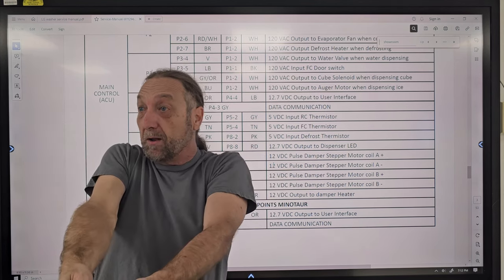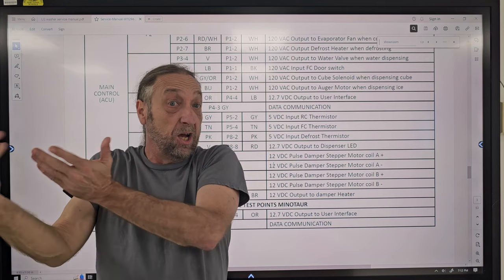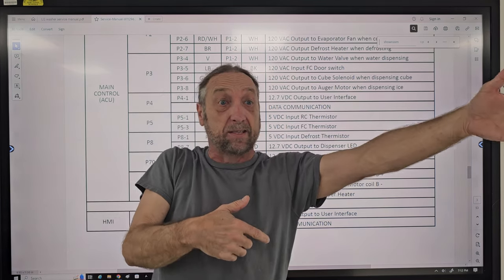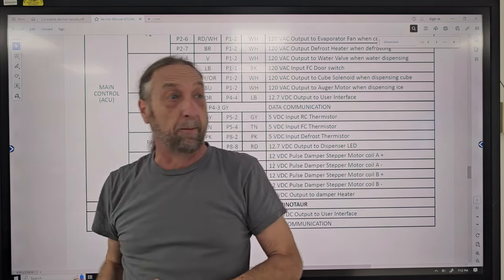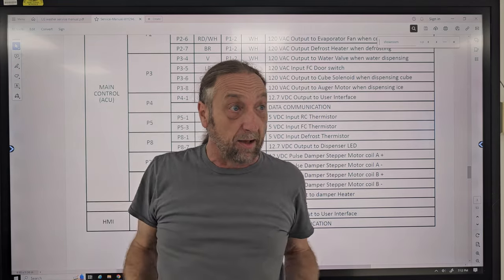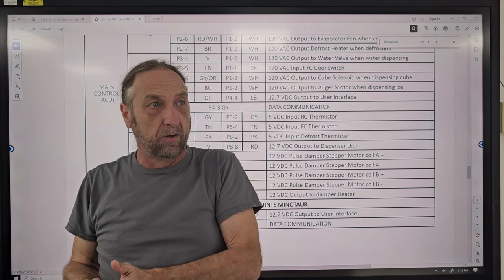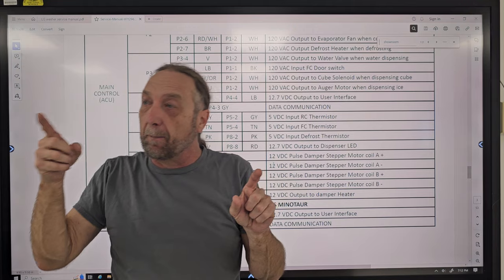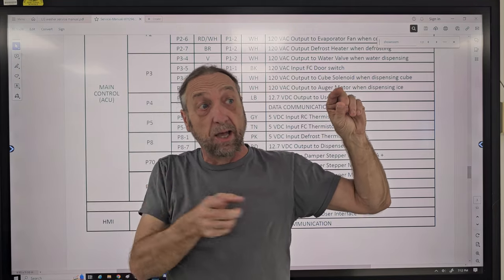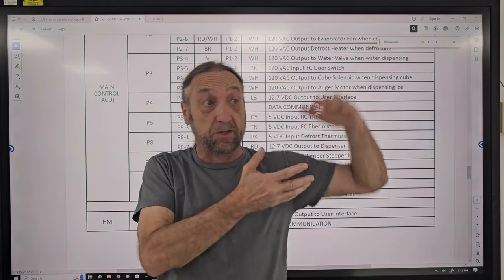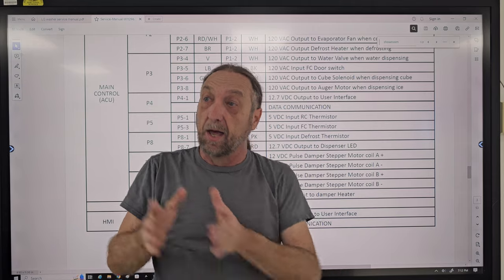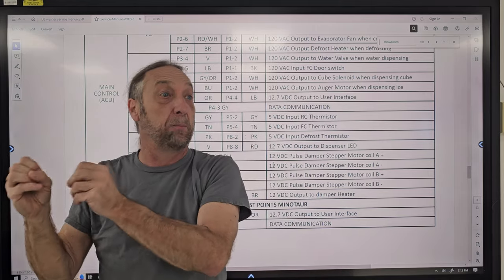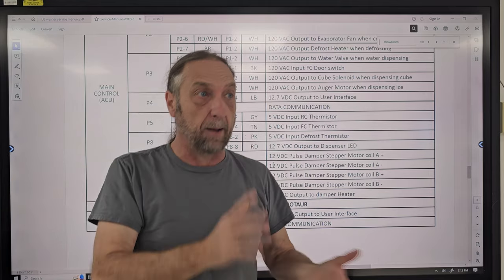Just like you put a meter on a thermistor to check its resistance, the board is checking the resistance. It says, hey, it's got 1,200 ohms, it's this temperature, or it's 30,000 ohms, it's this temperature. So that 5 volts going through that part goes faster or slower depending on the resistance going up or down, and the board sees that and mathematically converts it to temperature.